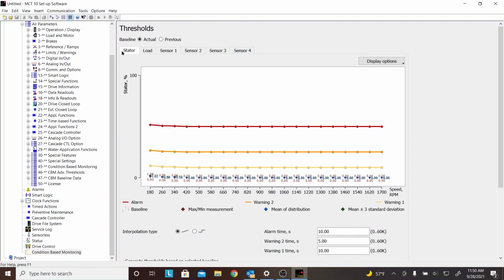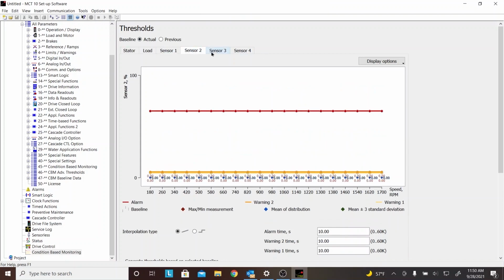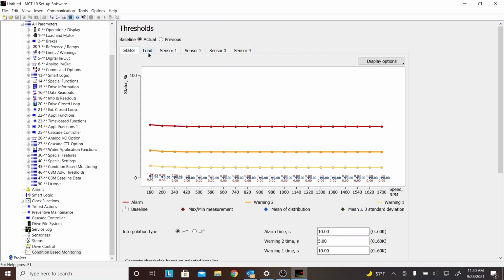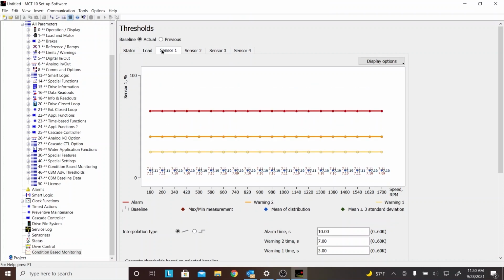In the threshold folder, we have a bunch of envelopes. And in these envelopes is where you set your limits for all your either stator, which is the winding integrity, the load envelope, or the sensors, which can be vibration sensors. Now these sensors, there's 4 of them currently that the drive can handle. And the sensors are an external device. Of course, the stator and the load takes its values from all the tools that are already inside the drive, such as the processors and CTs. But the sensors are an external device, such as a vibration sensor, and that has to be communicated to the drive. So we do that via the analog output of the sensor, and we stick that in the analog input of the drive. And I'll show you that when we program those.